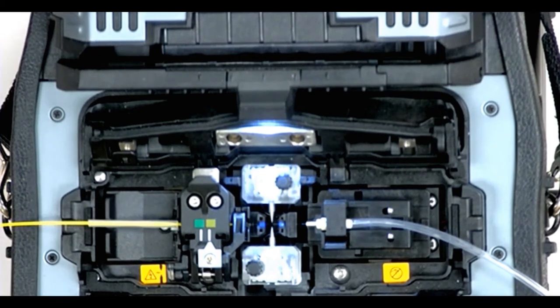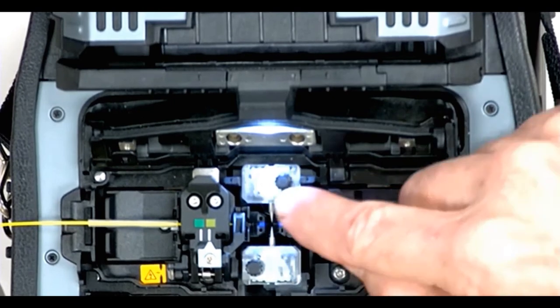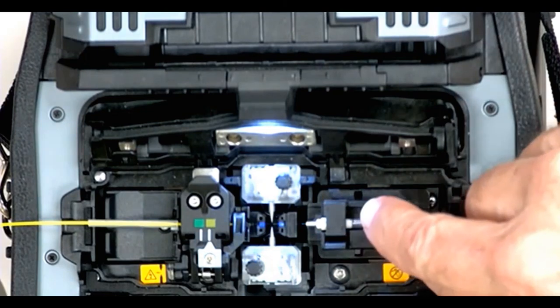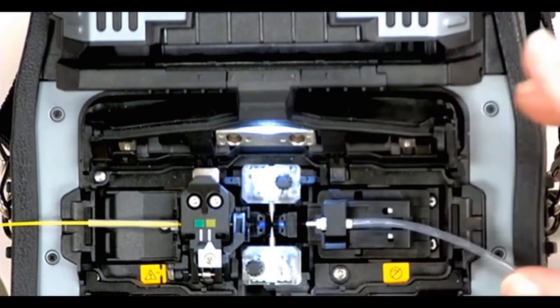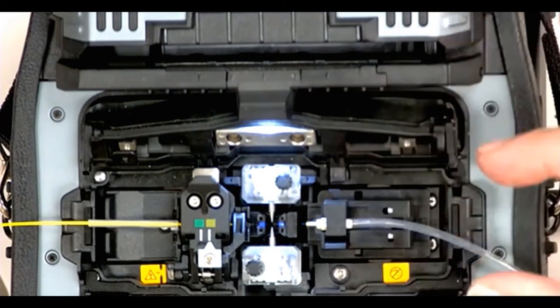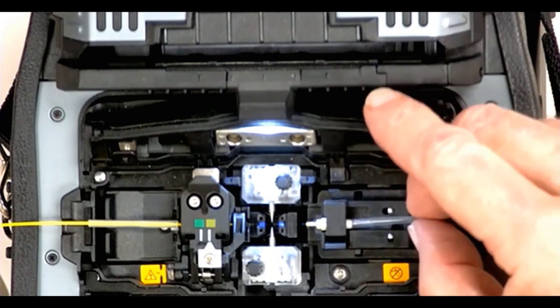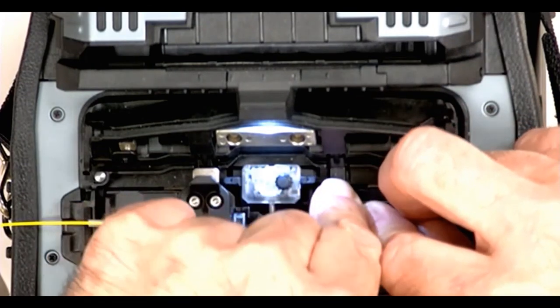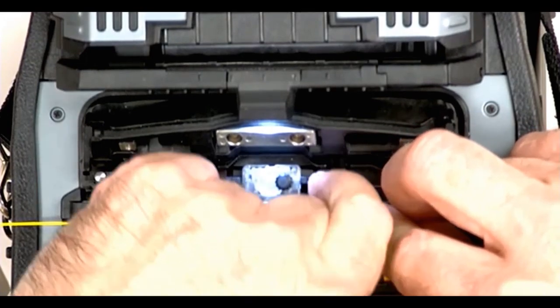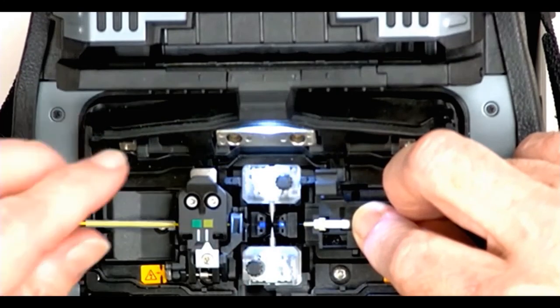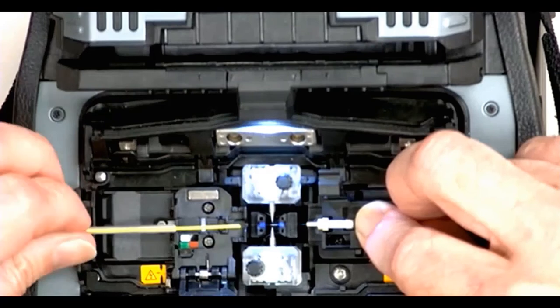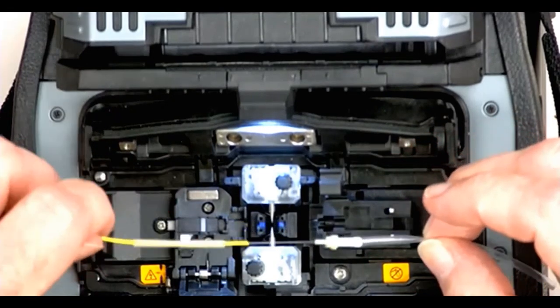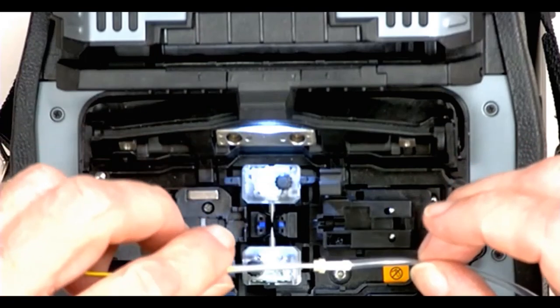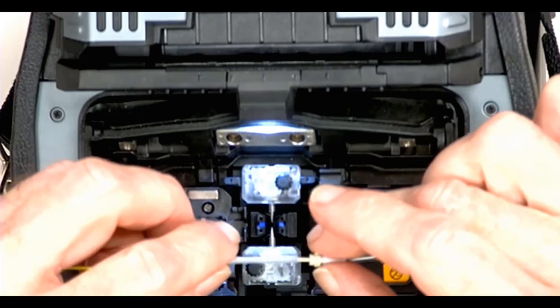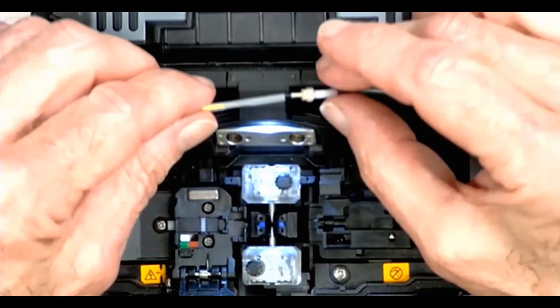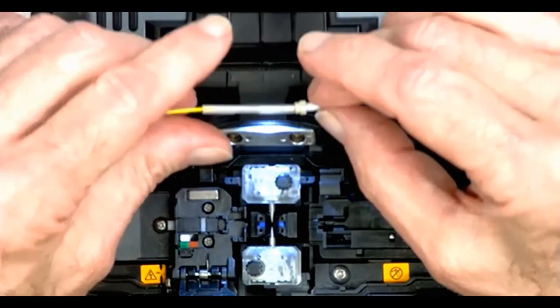Okay, so now I'm ready to take it out, and I have to protect all this while I'm doing that. So I'm going to press down on the fiber holder here, and you may even want to press down here with your pointing finger, but grab the tube with your thumb and forefinger. And while you're doing that, open the clamp. So now you can see the ferrule. Now I'll open this clamp, and now I pick it up, and let's let the sleeve slide down. And it has to go all the way over this little small diameter part of the ferrule, like that.